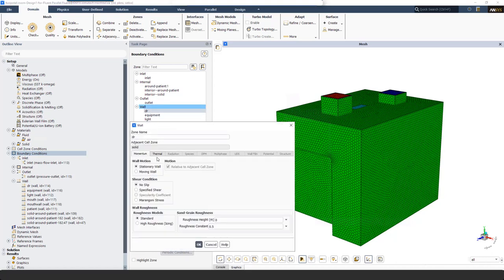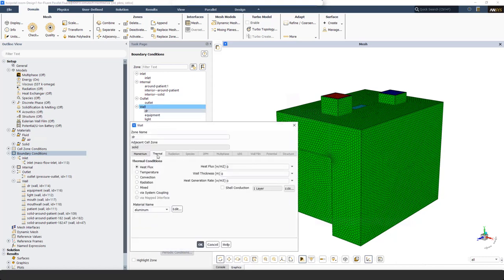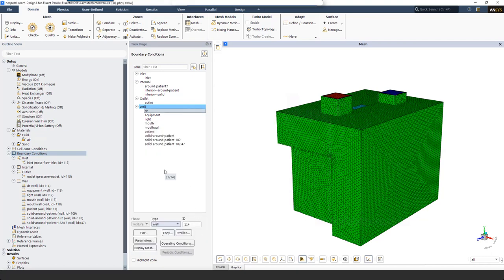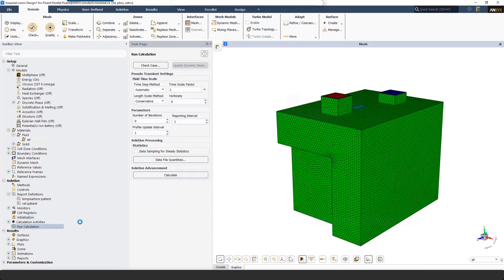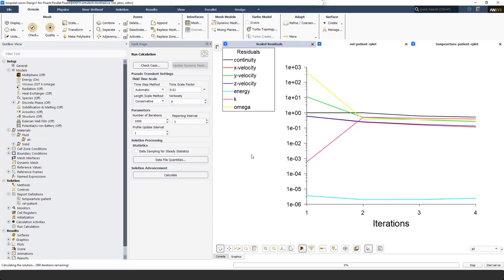I assign heat fluxes for the body of the patient, doctor, equipment, and light in the room. From the Thermal tab I set 60 watts per meter square for the doctor and do the same for the remaining wall boundaries with heat flux. Next, I initialize using standard initialization and run the calculation with a time scale factor of 0.01 for 1000 iterations. This will take a few minutes to solve; once done, I'll come back with the results.